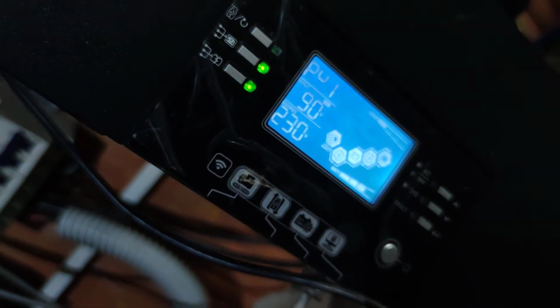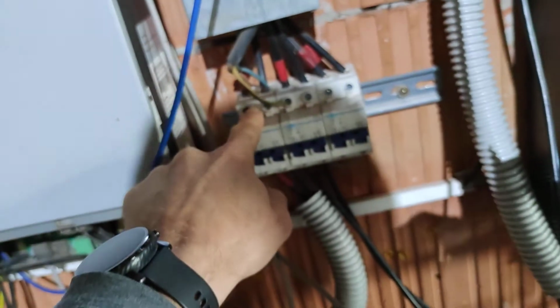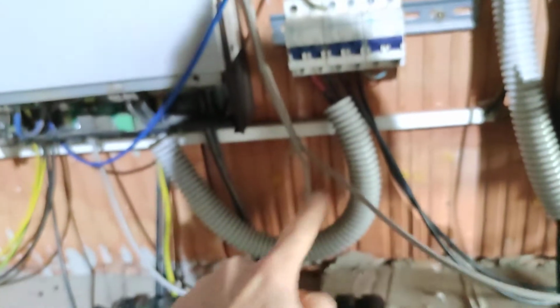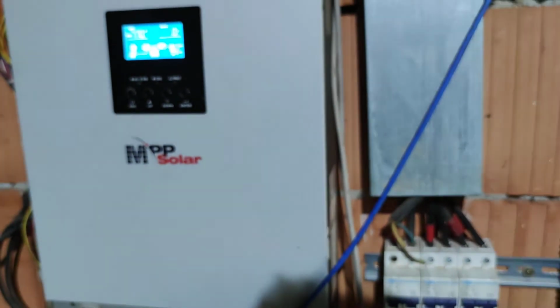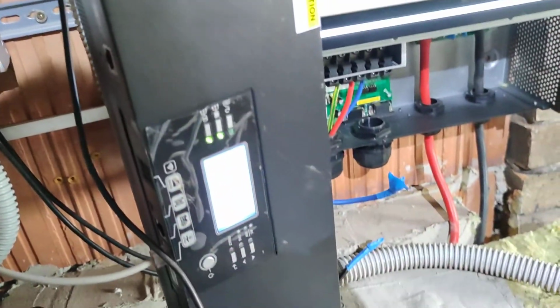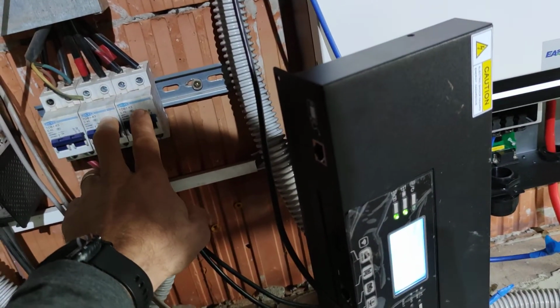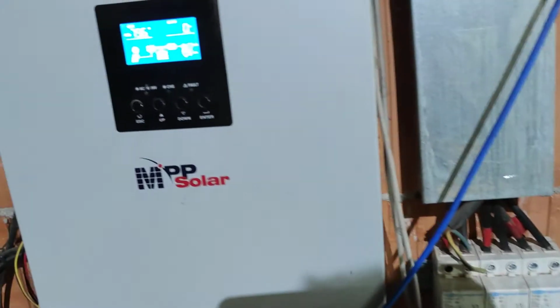So in order to fix this, to make it rethink, because the algorithm is obviously doing something wrong here, I have two breakers. The first breaker here goes to the first inverter, so to this one. The other two go to this one. Okay, let me now disconnect the two. As you can see, this one still produces 800 watts. Now, this one is okay, zero.